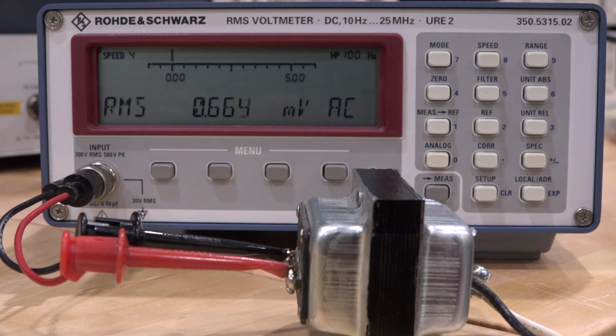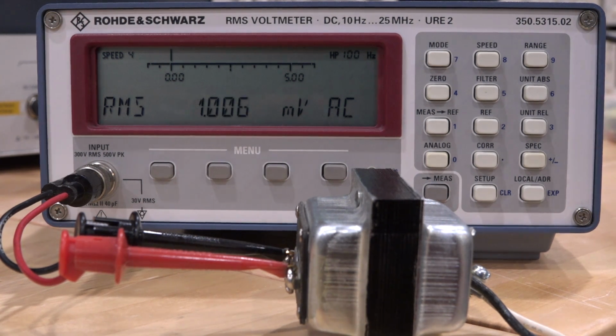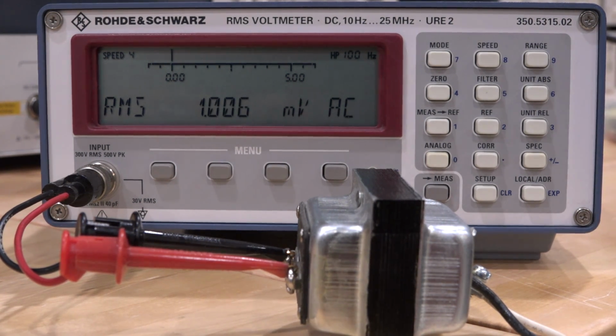So let's go ahead and use the Rohde & Schwarz URE2. So the voltage coming into my house tonight is around 124 volt RMS, and I have the output here directly connected to the input of this unit. Let's plug it into the AC line. Let's wait for this thing to settle down and see what we get. Look at that, 19.49 volt RMS. The turn ratio was about 6.44, and that's exactly what you would expect. It's verified by the measurements of the LCX200.